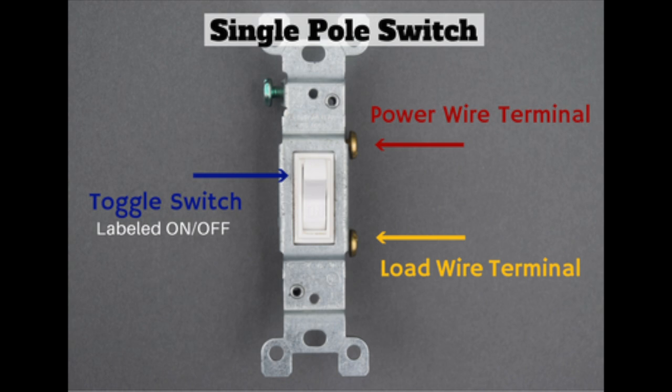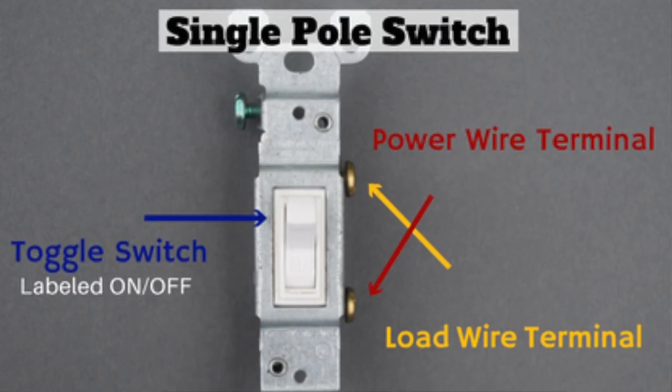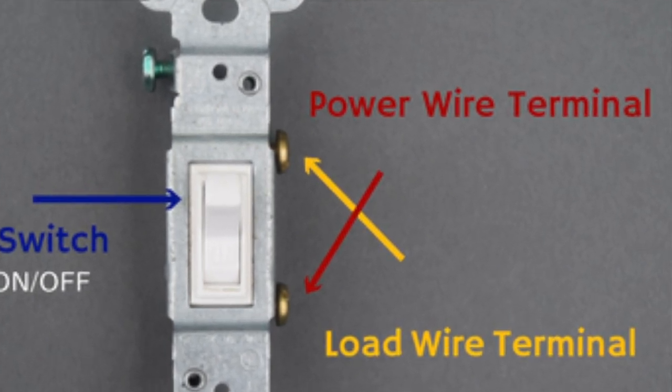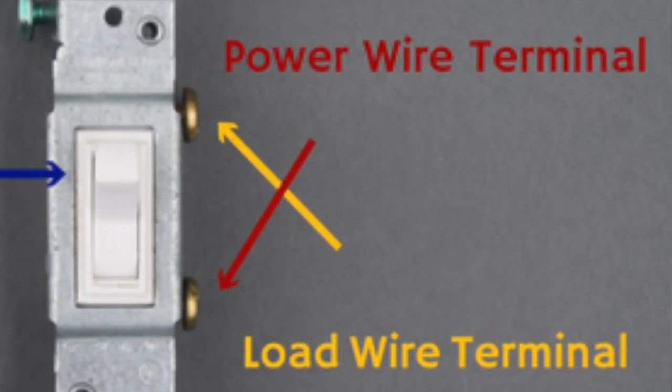Here is a single pole switch. Notice that there are just the two brass screws. It gets two wires. One of them will be the power wire and the other wire that you hook up will be our switch leg or load, which goes to the light. With a single pole switch, it doesn't matter which wire goes to which screw. It works either way.